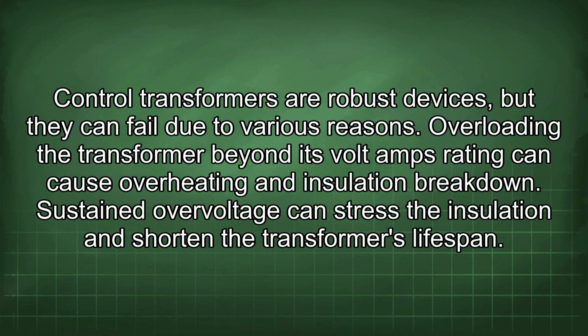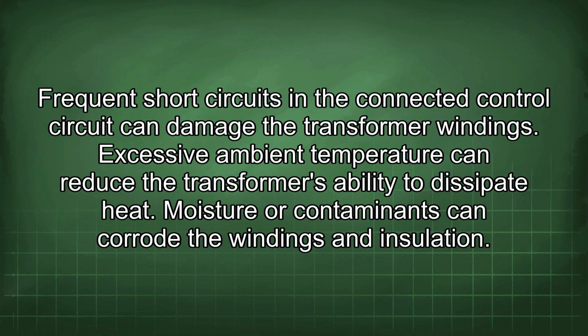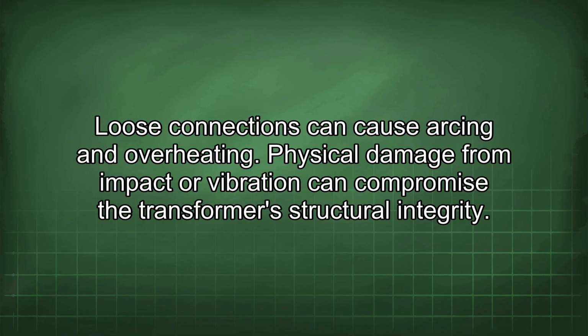Control transformers are robust devices, but they can fail due to various reasons. Overloading the transformer beyond its volt amps rating can cause overheating and insulation breakdown. Sustained overvoltage can stress the insulation and shorten the transformer's lifespan. Frequent short circuits in the connected control circuit can damage the transformer windings. Excessive ambient temperature can reduce the transformer's ability to dissipate heat. Moisture or contaminants can corrode the windings and insulation. Loose connections can cause arcing and overheating. Physical damage from impact or vibration can compromise the transformer's structural integrity.